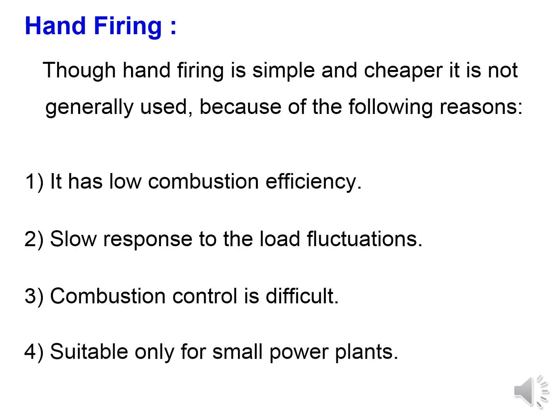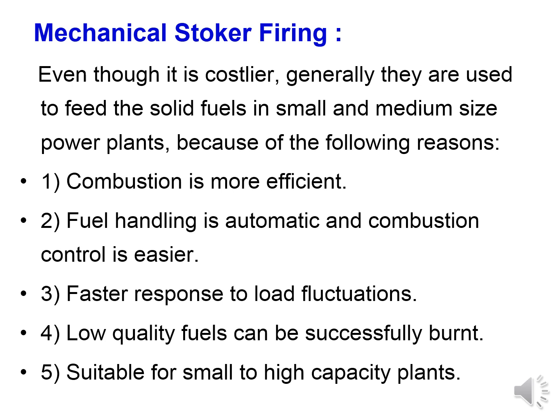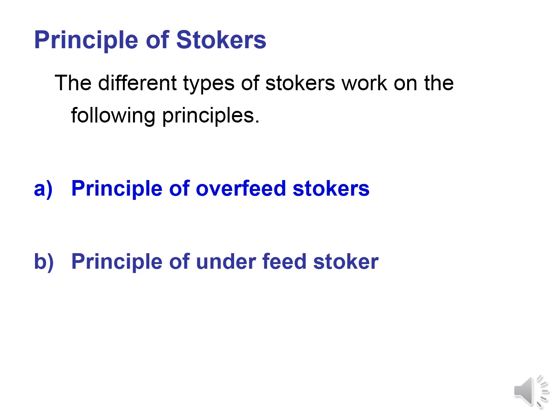Hand firing is simple and cheaper but is not generally used due to low combustion efficiency, slow response to load fluctuations, and difficulty in combustion control. Mechanical stokers are used instead because combustion is more efficient, fuel handling is automatic, response to load fluctuations is faster, low-quality fuels can be successfully burnt, and they are suitable for small to high capacity plants. The two types are over-feed stoker and under-feed stoker.